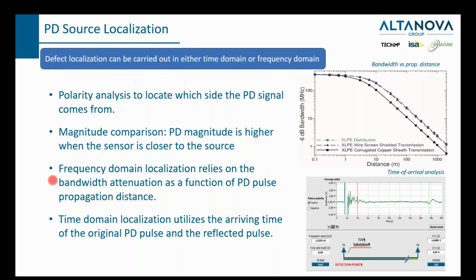The last two methods are a little bit more complicated. Frequency domain localization uses the bandwidth to check where the signal comes from. Using a cable as an example, as we show here, the PD signal bandwidth at the initial point is a very high ultra wide band signal. The bandwidth is higher than hundreds of megahertz or even in the gigahertz range. After a certain distance of propagation, the bandwidth will decrease. And with the measured bandwidth, we can roughly estimate where the PD source is.